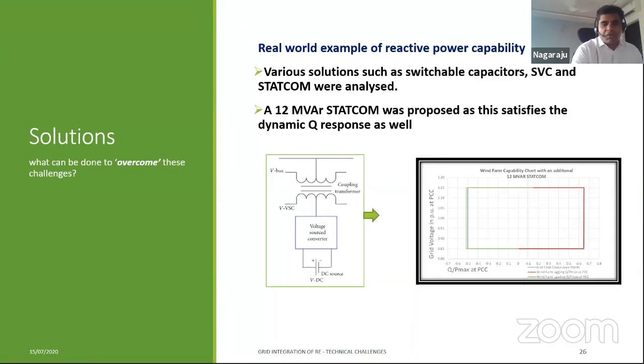For that, what we proposed is a 12 MVAR STATCOM to be installed at the connection point, just in parallel to the wind farm. It can now make the reactive power support fully compliant. You can see that the entire capability is either within or exceeding the requirement. So that is one example I wanted to show you.